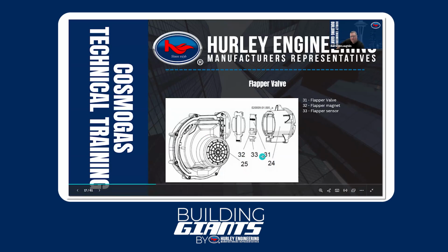So all of the burners come with these 3 components: the flapper valve, the flapper magnet, and the flapper sensor. And that's strictly to prove that that gate is closed and we can't recirculate exhaust gas back into our cabinet. It also checks that they're open when they're supposed to be open and closed when they're supposed to be closed. And it's absolutely necessary whenever you common vent any burners. And again, inside our cabinet, all 4 of our burners, or up to 4 burners, are common vented.